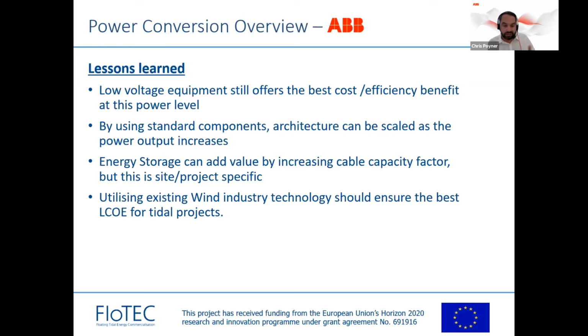By using standard components, the architecture can be scaled as the power output increases. The benefit of our equipment is the generators come in frame sizes, so as the power requirement goes up, you go up a different frame size. We have considered PM technologies, direct drive, getting rid of gearboxes. As it stands at the moment, it wasn't sensible for this project, but moving forward that's definitely something we'll consider. So the benefit is as the power goes up, the product goes up, but it's still essentially the same product we're using.